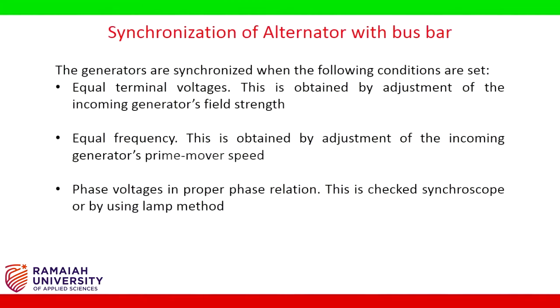The generators are synchronized when the following conditions are set. Equal terminal voltages. This is obtained by adjustment of the incoming generator's field strength. Equal frequency. This is obtained by adjustment of the incoming generator's prime mover speed. Phase voltages in proper phase relation. This is checked by synchroscope or by using lamp method.